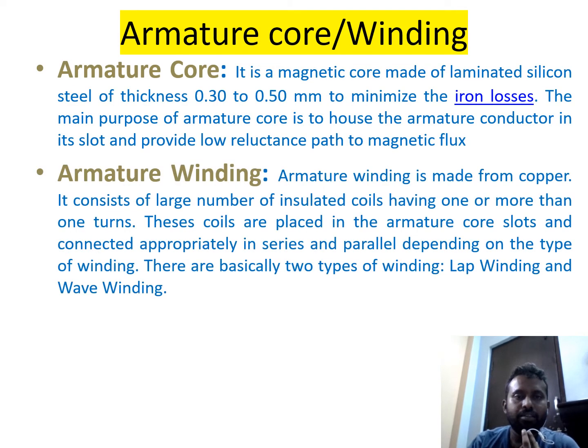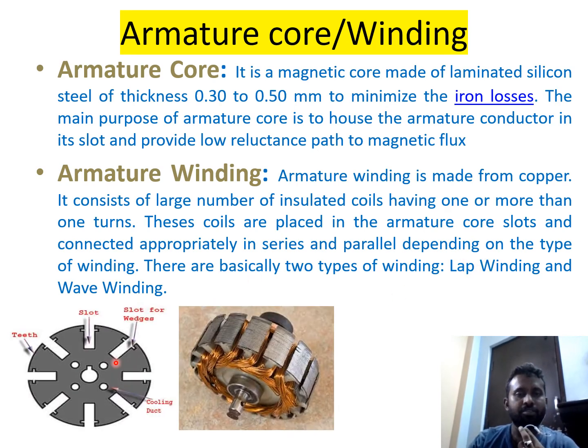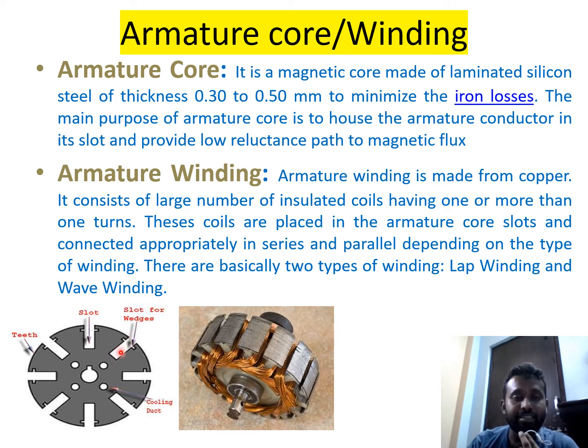The armature core is a magnetic core of laminated silicon steel of thickness 0.3 to 0.5 mm, laminated to minimize iron losses. Its main purpose is to place the armature winding and provide a low-reluctance path to the magnetic flux. The armature winding is made of copper with a large number of insulated coils connected in lap winding or wave winding. The armature core has wedge-shaped slots with cooling ducts to prevent wires from slipping due to centrifugal force and to reduce heat from rotation.